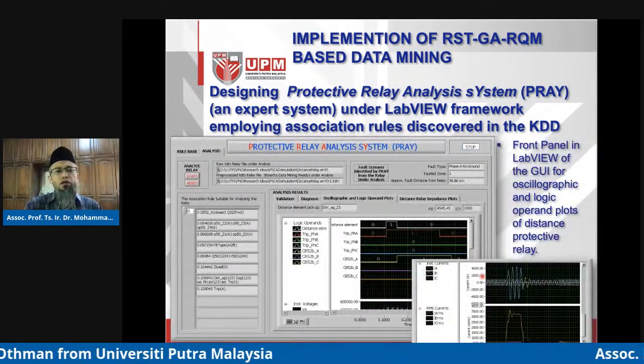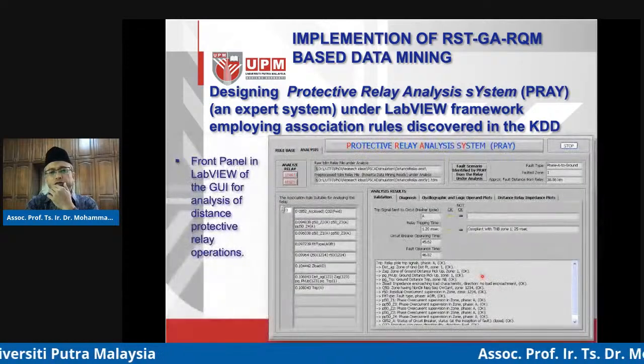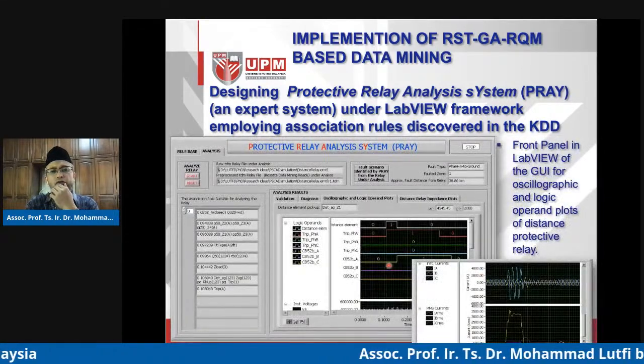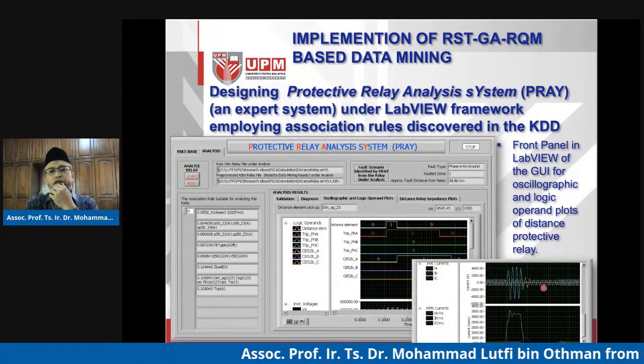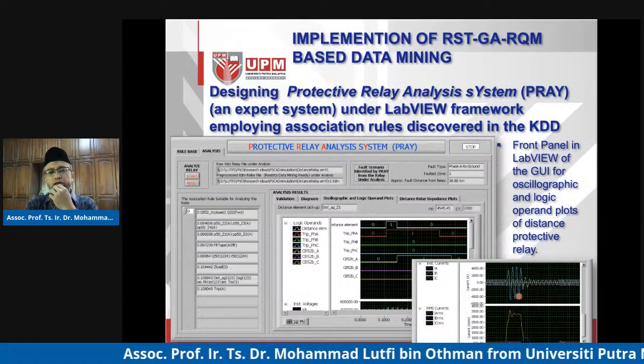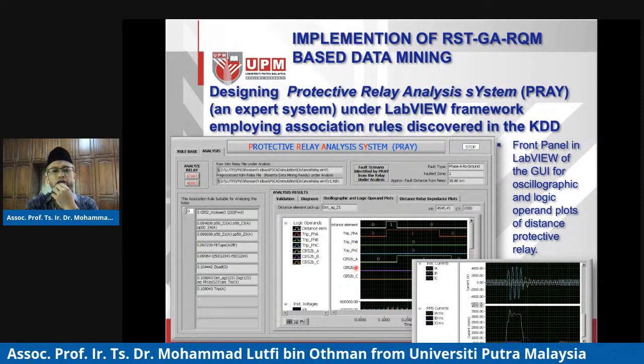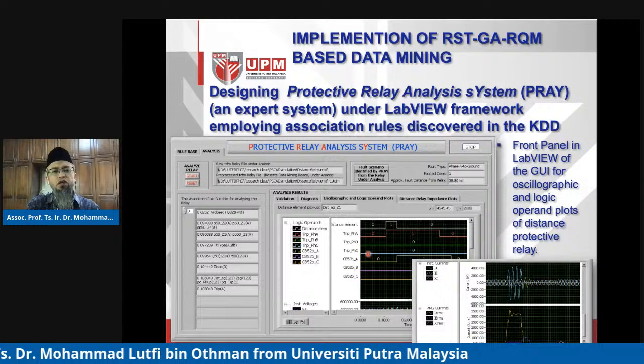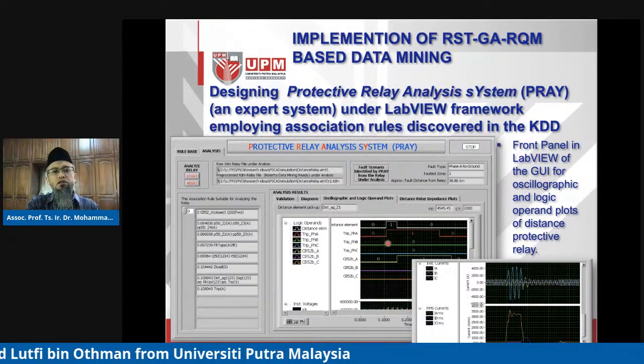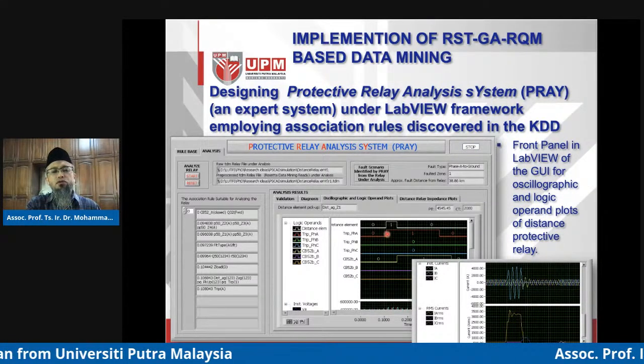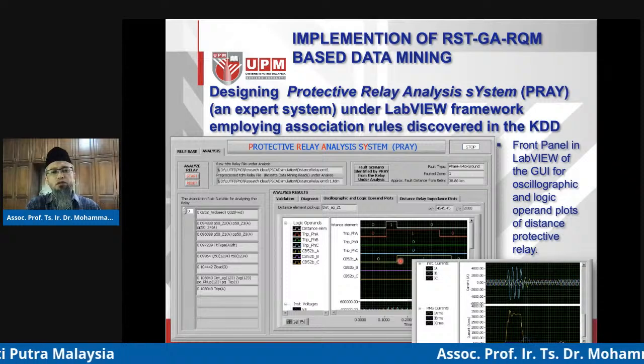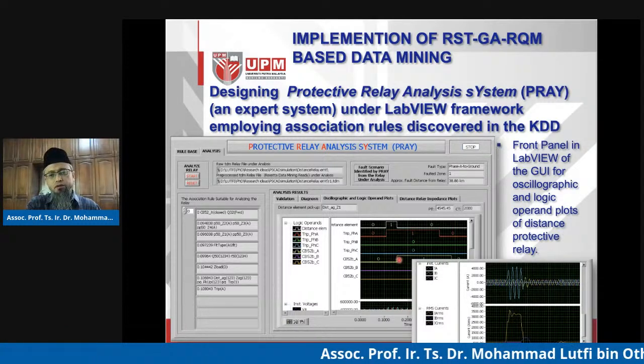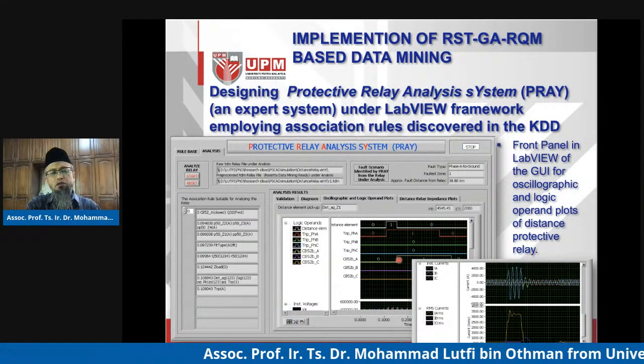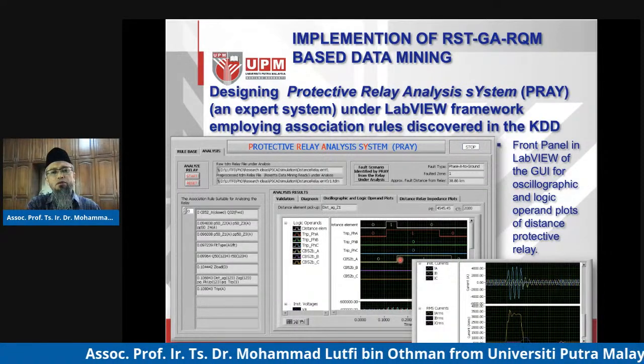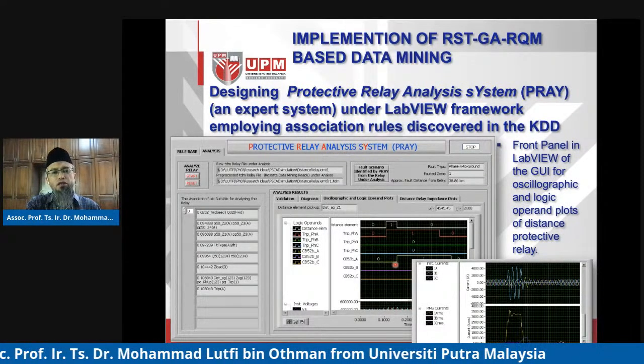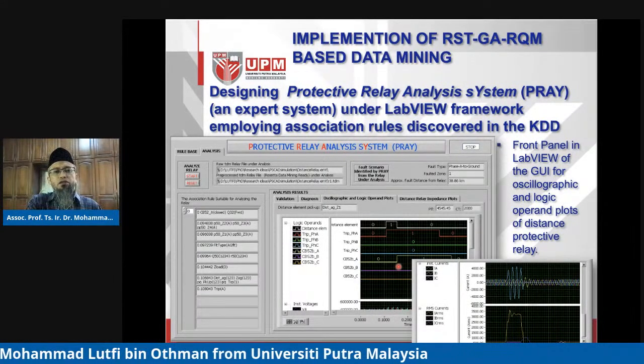We can reconstruct from the data we got from the relay to see how it behaved, plotting back the voltage and current, and see how the internal function of the relay behaves. The relay managed to detect a fault, and a tripping signal from the circuit breaker has been given into the relay to confirm that tripping has taken place. So that's a good relay.